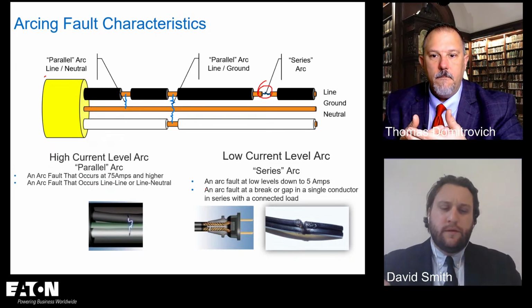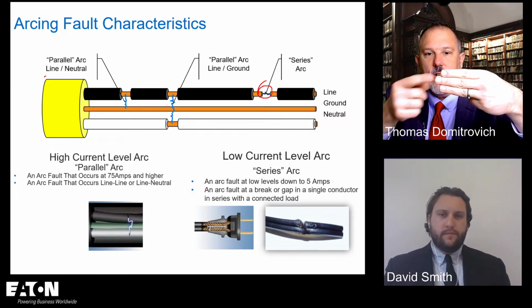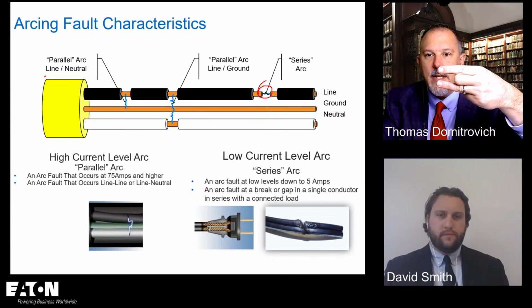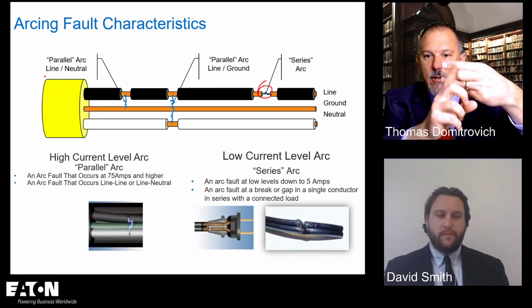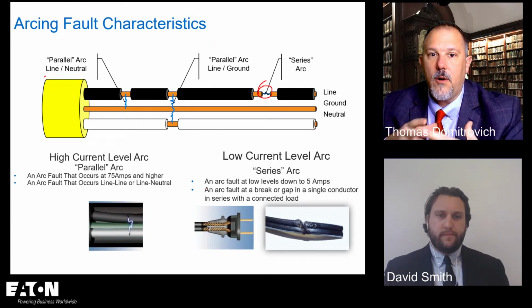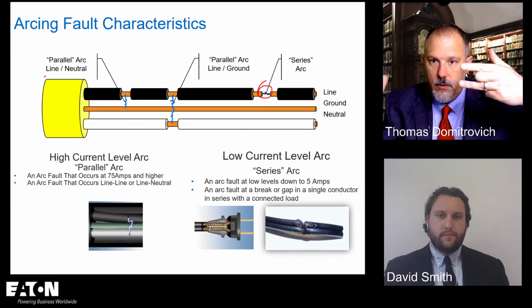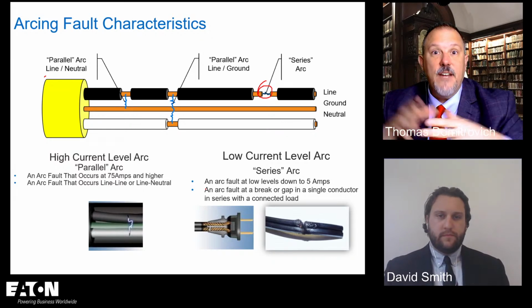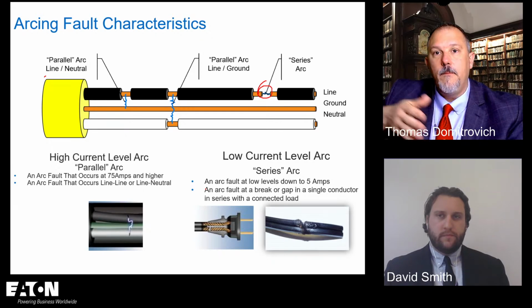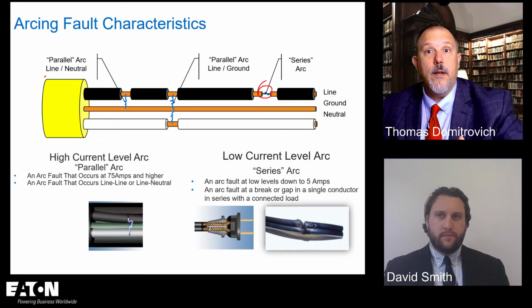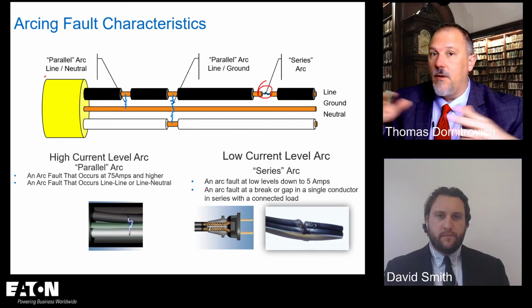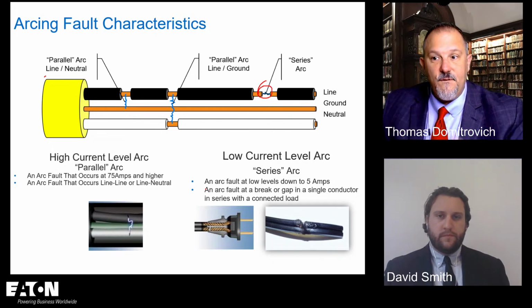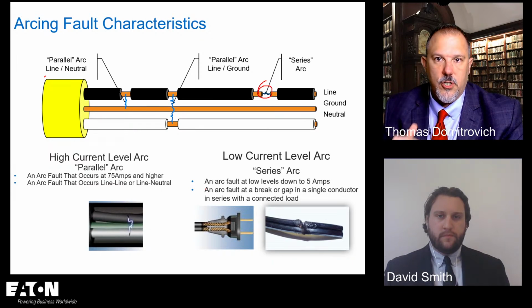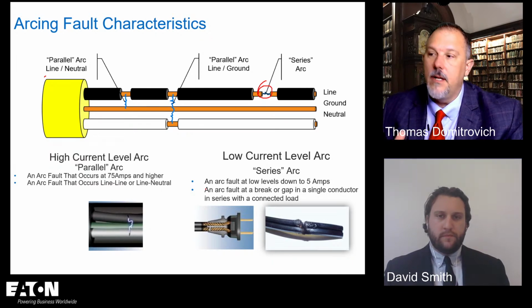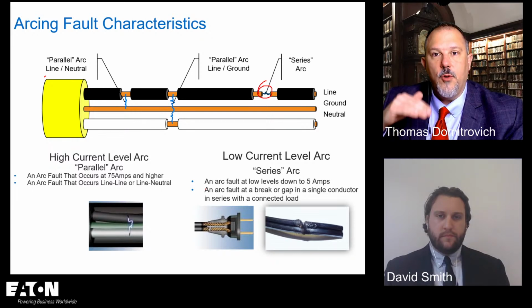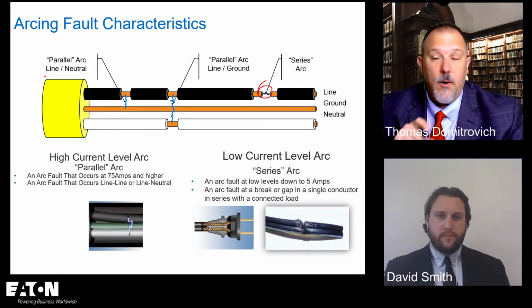So when I go parallel, I take my 3 conductors, I take this equipment grounding conductor out, and I cause an arc right across here. That trigger point, because it's a parallel arc, parallel with the load, is 75 amps because you're shorting the system. UL did research and measured the available fault currents at all these different receptacles, and they found the lowest available short circuit current was 75 amps. So we make sure that we can detect that, which would be a parallel arc.